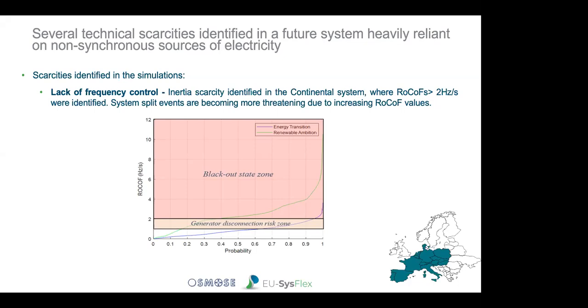EDF completed analysis for the continental European power system and found an inertia scarcity, which can cause very high rate of change of frequency, in some cases greater than 2 Hz per second, indicating an issue with frequency instability. There were also many instances where the frequency nadir, the lowest level frequency reaches following a disturbance, approached load shedding levels, which we want to avoid. System split events were also becoming more threatening due to increasing rate of change of frequency values, particularly where the Iberian Peninsula splits from the rest of the European power system.